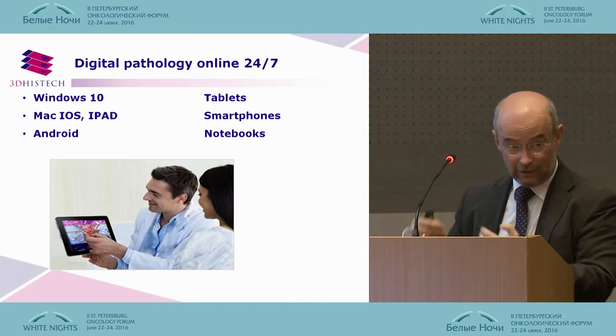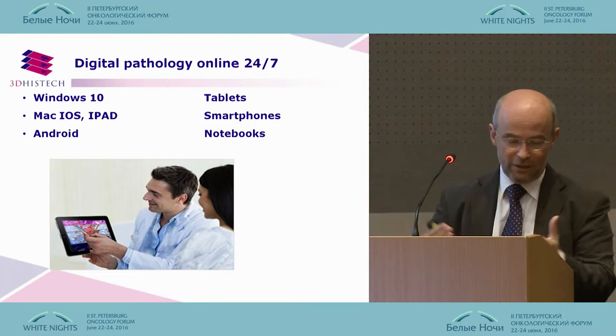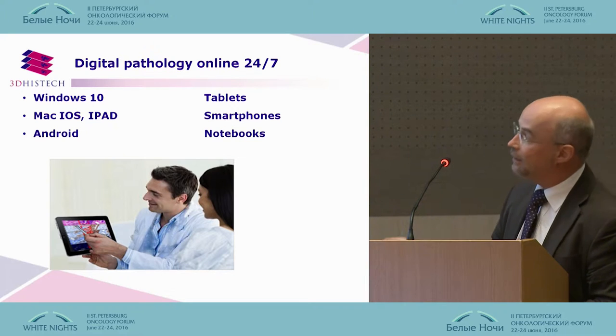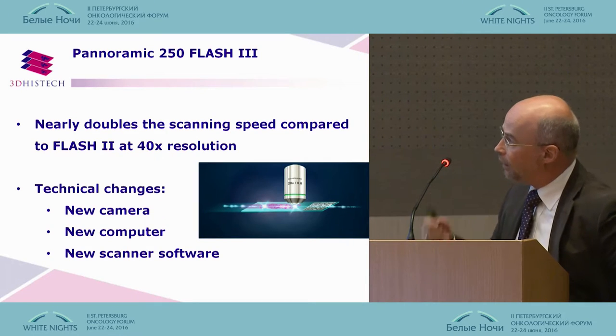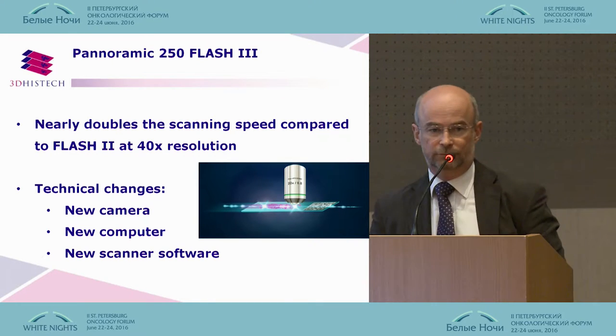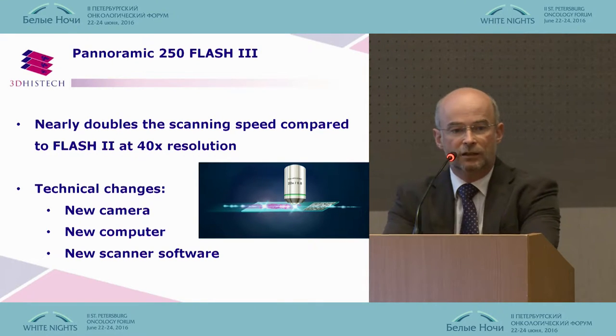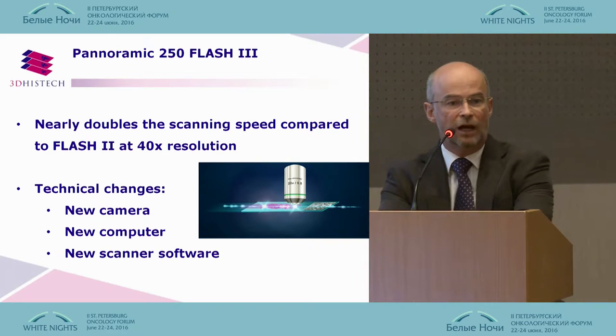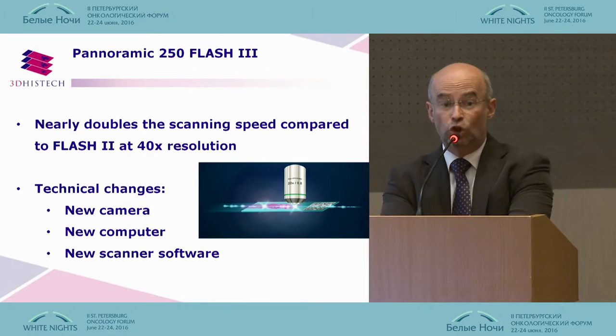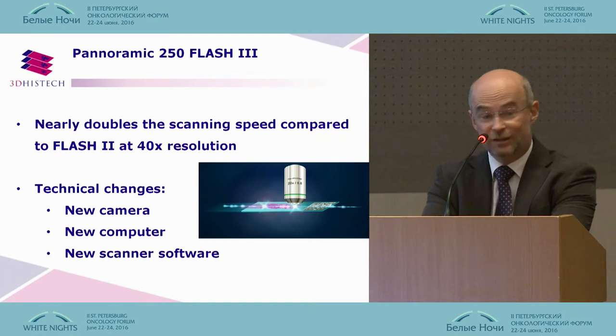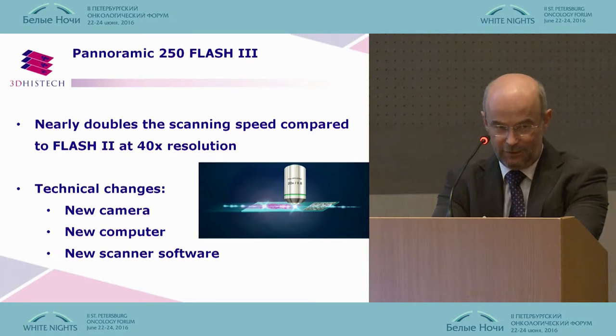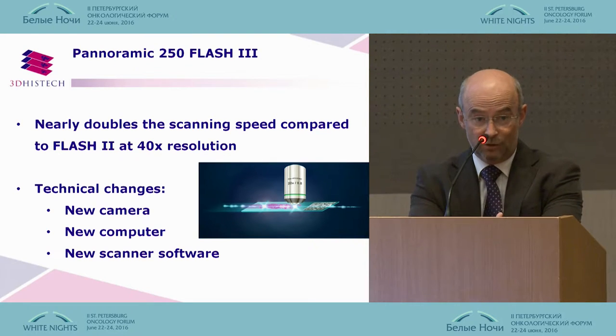Pathology images are really numerous. In your departments, every day 300, 500, 1,000, or 2,000 different hematoxylin and eosin stainings are produced. If you want to use digital slides for digital diagnosis, it has to be comparable with the optical microscope, meaning the optical resolution must be at 40x or larger. We at 3D Histech have always said 20x is not enough — you need 40x to see the dysplasia, to see bacteria, to see gram-negative positivity, and it must be standard.